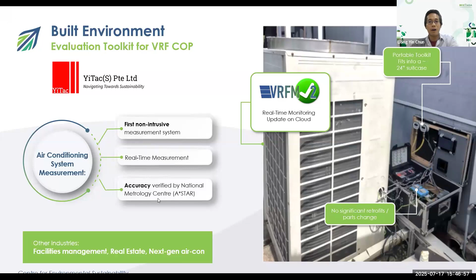This is just a very simple schematic to show you how this system works. Basically, it's very similar to a chiller plant, whereby we have to measure the supply and return temperature, and we measure the flow rate. Similarly, in this case, for the refrigerants, we measure not just the temperature but also the pressure. From the temperature and pressure, we are able to tell the enthalpy, or the energy per kilogram of the refrigerant, running between the condenser and the indoor evaporator.